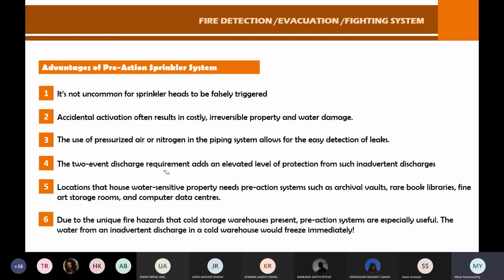The use of pressurized air or nitrogen in the piping allows for easy detection of leaks. The moment the leak is detected, the valve can be controlled. First, there will be instant investigation whether it's actually fire or someone's mistake. If there is a fire, the BMS will open up the valves and the water can come in. But if there is a mistake, it can stop the valve, keep it stopped, and you will be safe. So that is how fast it can be.